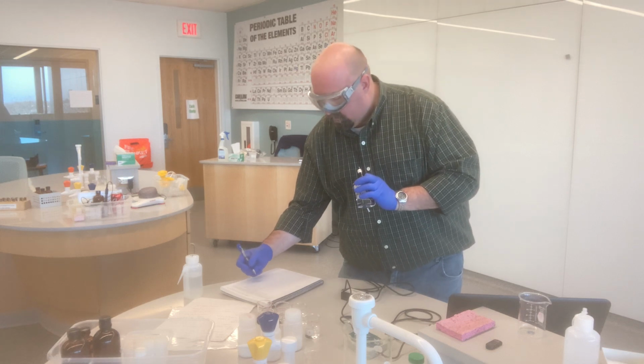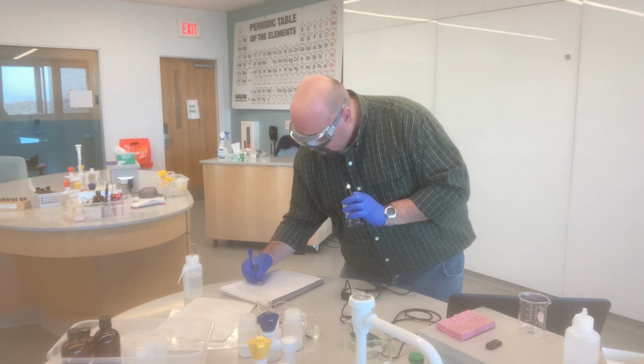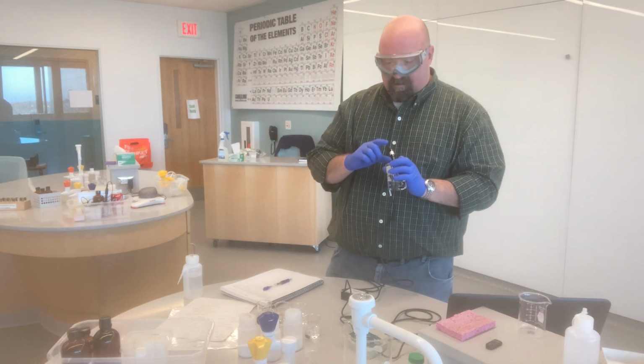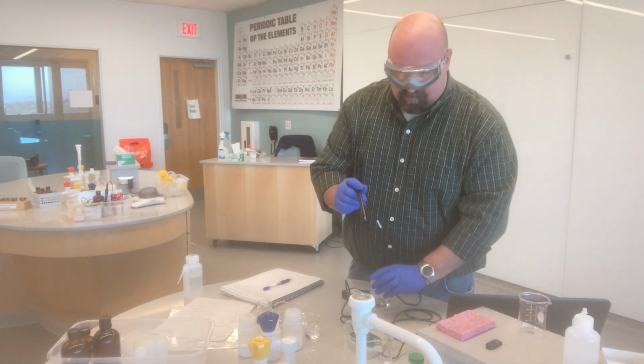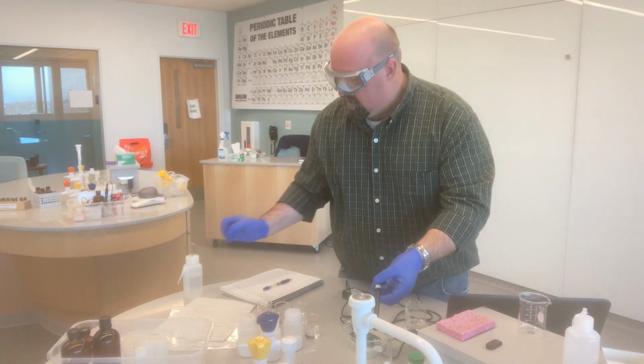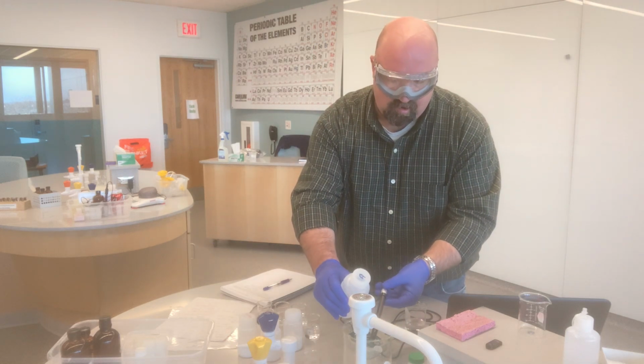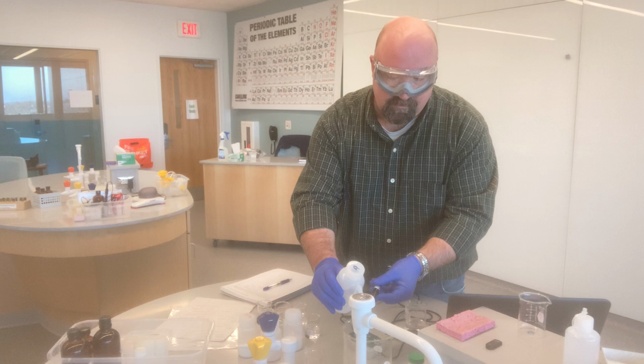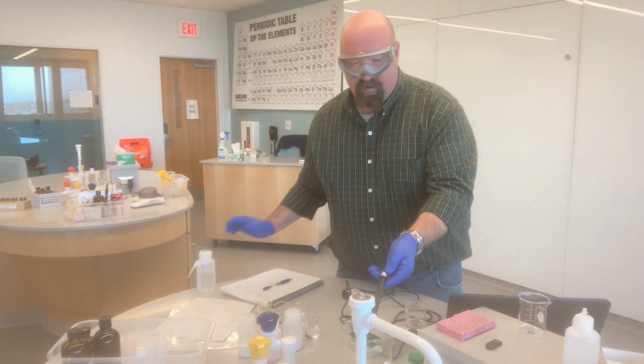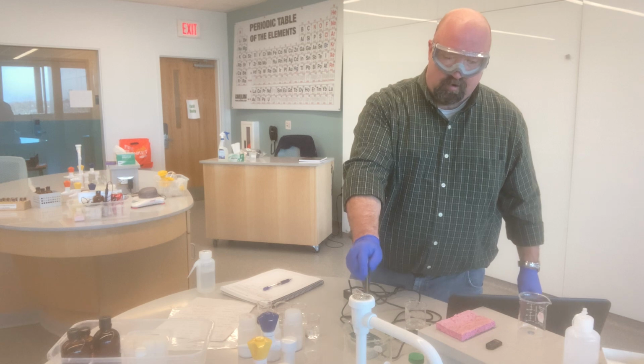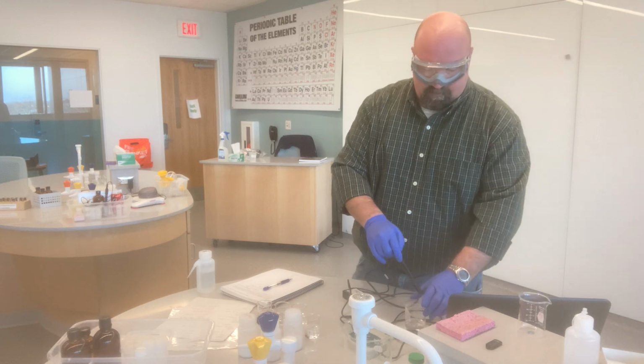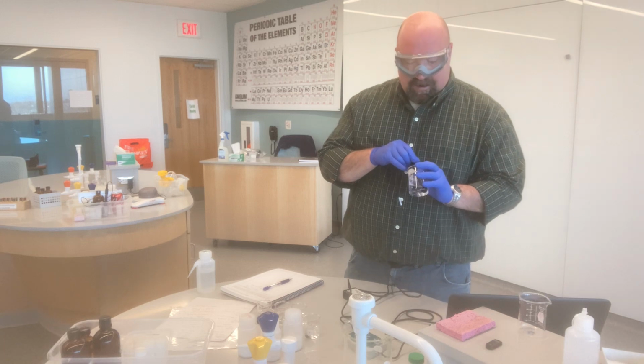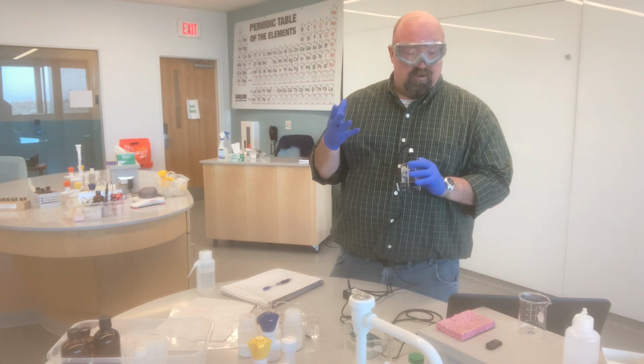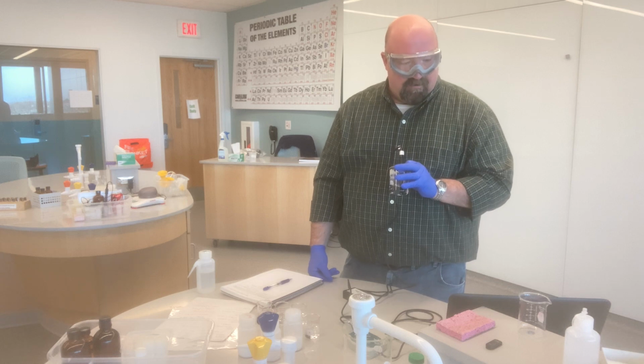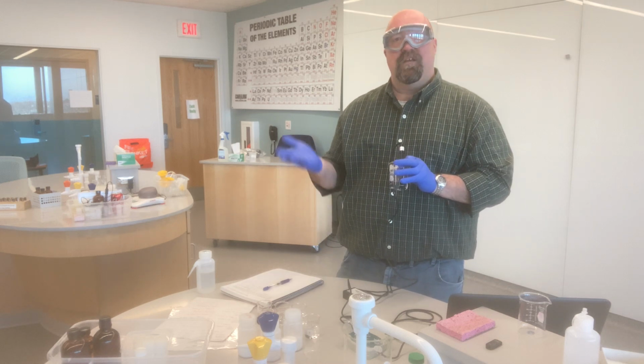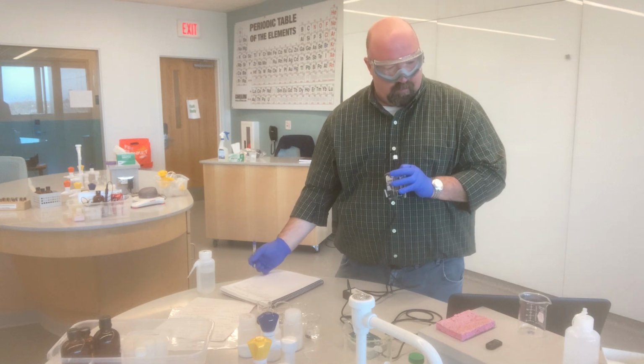For 4,215. Again, these are all microsiemens per centimeter. Now, some of you are hopefully asking, well, this is outside the calibration range. With turbidity, we had to dilute a sample down so that it was within the calibration range, which was true. For the turbidity probe, we didn't necessarily know if the instrument was accurate outside of our calibration zone. For this one, we do. We just know that about this instrument, that it is accurate outside, and so we are comfortable taking measurements that are above our actual calibration window.